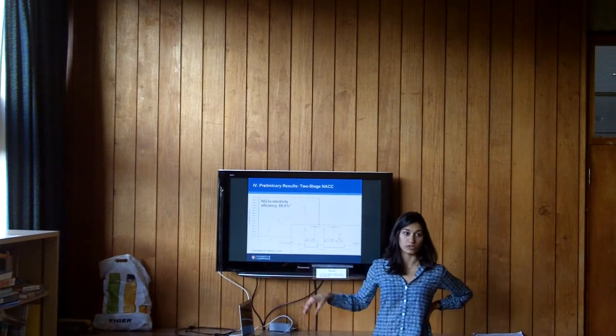These are some preliminary results showing a natural gas to electricity conversion efficiency of around 68%, which agrees really well with literature. In a standard gas turbine, efficiency is about 55 to 60% — specifically 57% for the particular model the PBFHR is being designed with in the US. This is the thermodynamic model — the TS diagram I showed earlier, but with more stages.